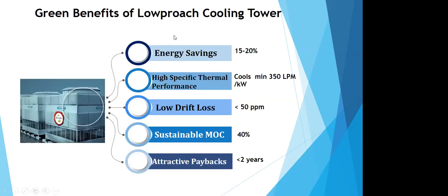So in a nutshell, the benefits that arise from the low approach cooling tower are, obviously, energy savings, a high thermal performance in the range of 350 liters per minute per kilowatt, and low drift losses, which is around 0.005% of the circulating water rate. The MOC is 40% reusable and hence a sustainable product, with an attractive payback of 2 years. It not only helps to reduce your energy consumption, but helps you earn green points, which will help you certify your building as a green building. Low approach cooling towers can help you earn around 8 green points for your green building, which will help you get the higher certification.